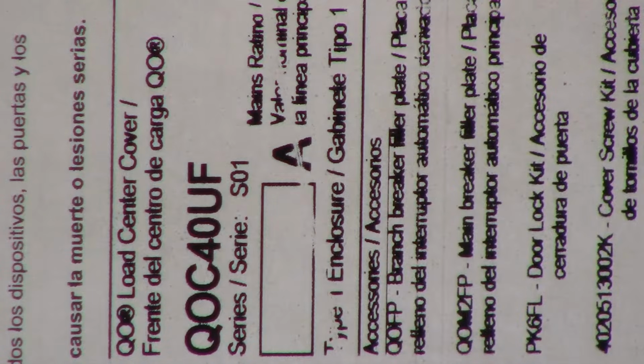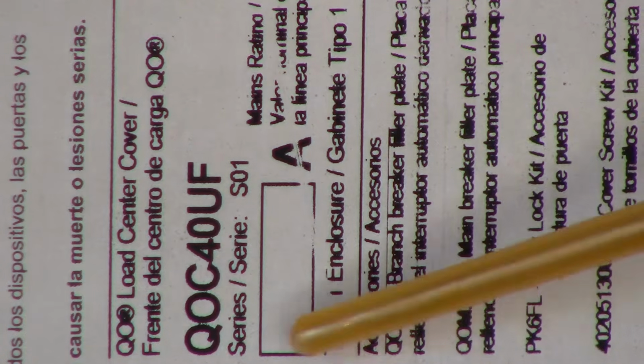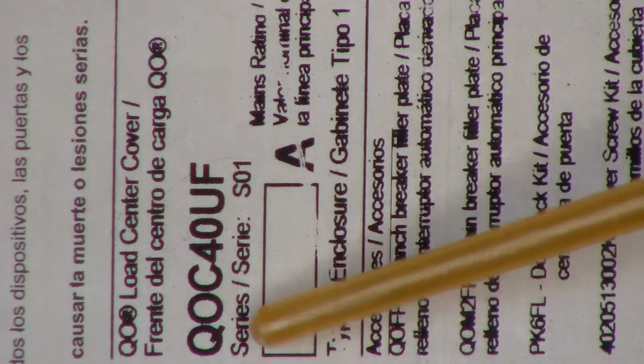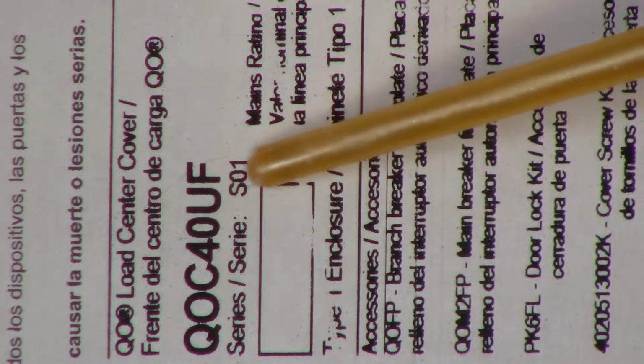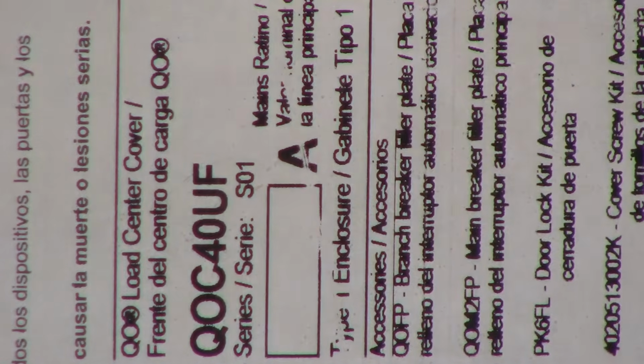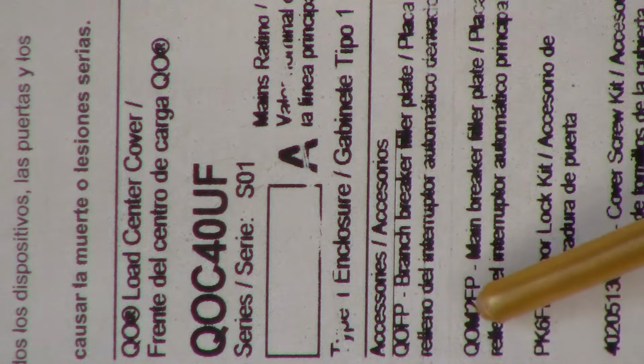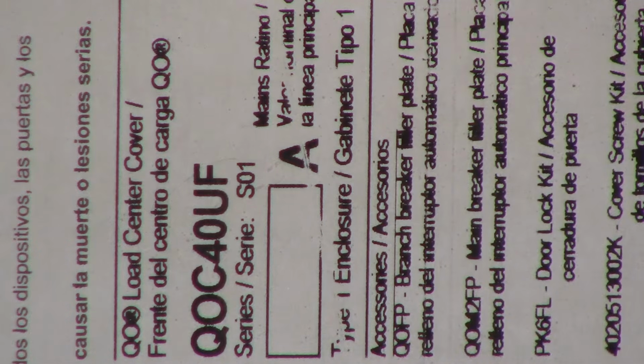And this information right here is going to tell us this is the model of the panel, which is a QOC40UF, which tells us that this is a 40 circuit panel. We can also look at the numbering on the cover here. We see that there's 40 circuits here. Also, when we look at it here, this is a type 1 enclosure. Okay, so this cabinet, together with the cover, is a NEMA type 1 enclosure, dry location application, and of course that's where it's at, so that's important if it's installed in a wet location. And here it says it's a type 1, you know that that's a dry location.